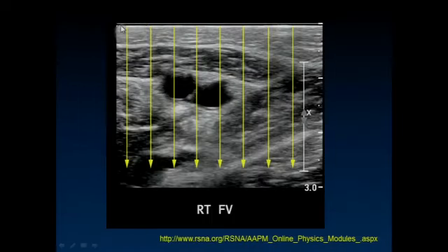When we see an ultrasound study done with the linear array, it's usually very obvious because the face plate is straight right across the front. And the one thing I wanted to point out to you in terms of the linear arrays is that our loss of resolution as a function of depth is less than it is for the curved linear arrays, where the ultrasound beams are diverging as they get further away from each other.